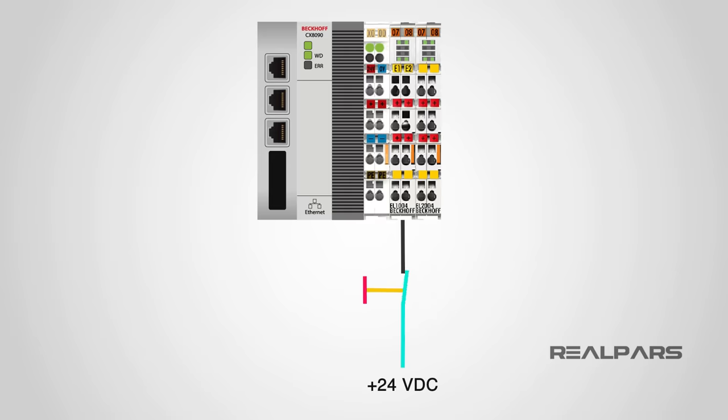Now, imagine the switch is back to the normal mode, but this wire gets disconnected for some reason. What happens now? In this situation, the healthy signal will be lost, and the PLC sees that as someone pressing the switch, right? So it shuts down the whole system.